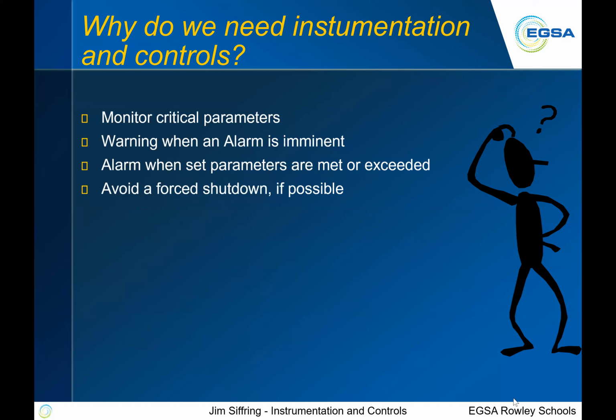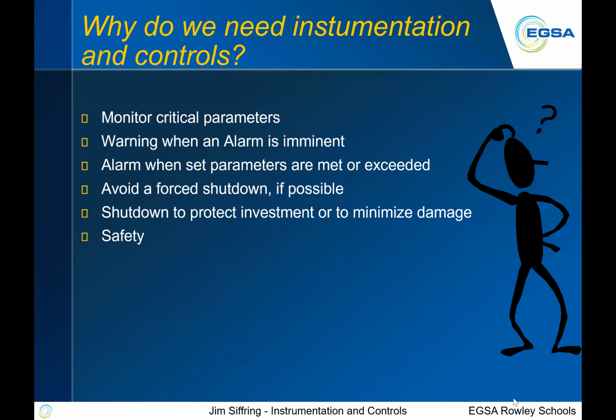So what we really want to do, though, is avoid a forced shutdown if at all possible. But we do want to shut it down if we want to protect the investment, to minimize damage, to increase safety, whatever it happens to be. There are a few exceptions to that. Typically with fire pumps, there are very few shutdowns. If a fire pump is running, typically you want it to run and give its life for the cause. But safety is really the final thing that we're trying to get to. So what we want to do with all this instrumentation and controls is provide information to us.